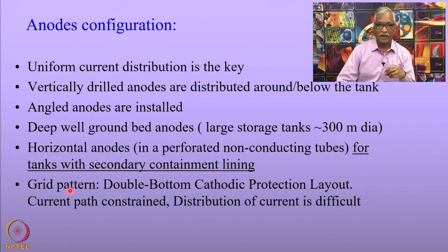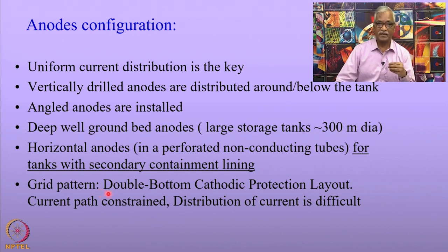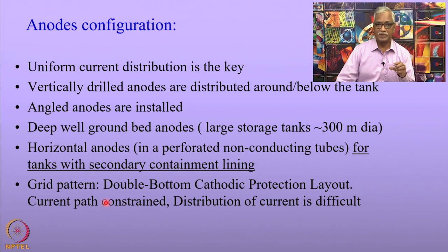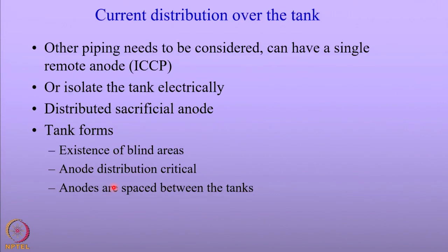Deep grid pattern anodes are also used where double bottom cathodic protection layouts are required, but the problem here is the current paths are constrained, making current distribution very difficult. We have talked about current distribution at the bottom of the tank, but the current distribution over the top of the tank is also equally important.